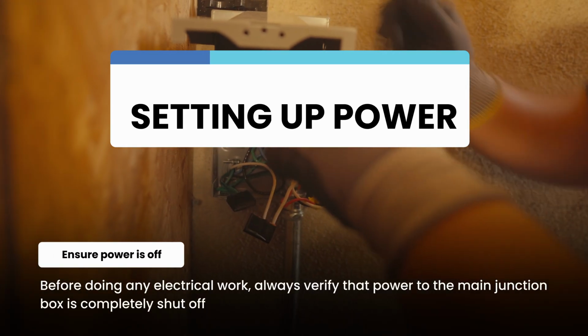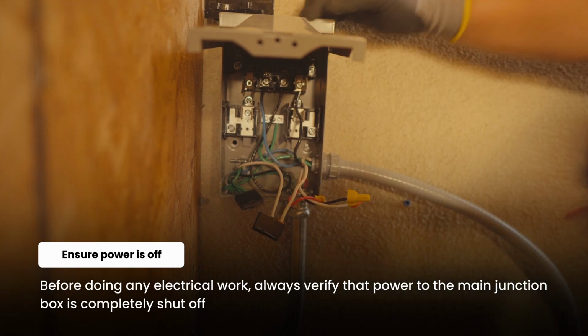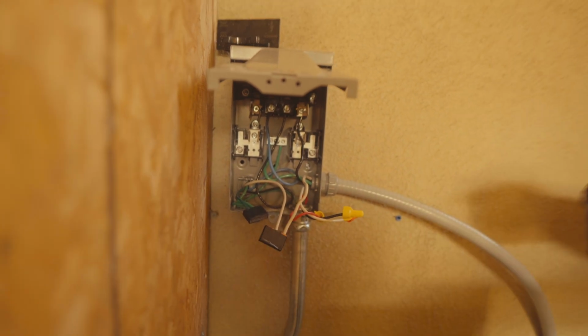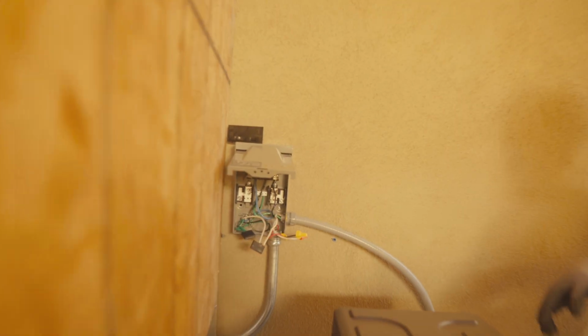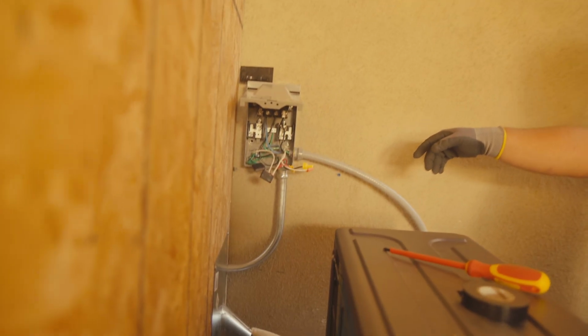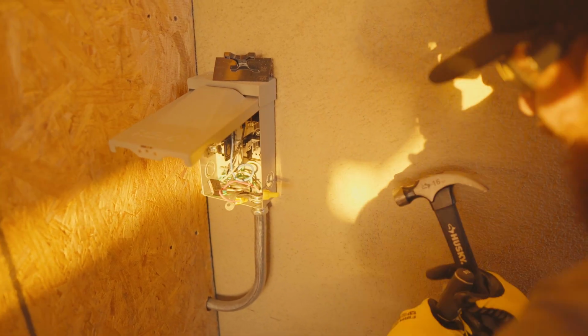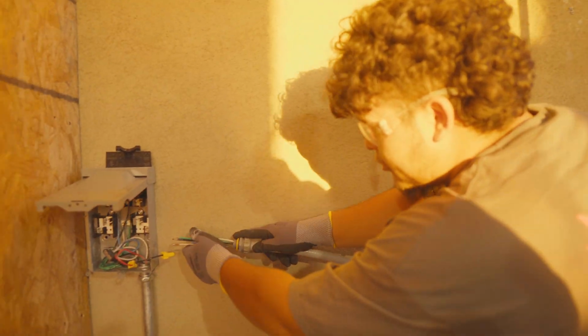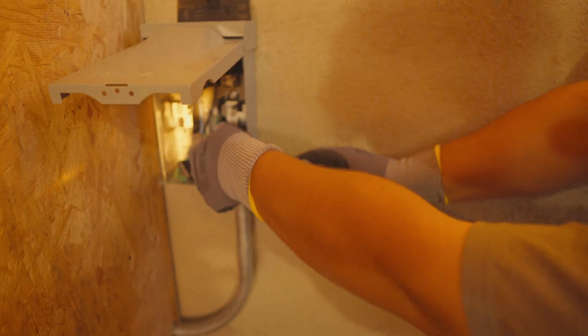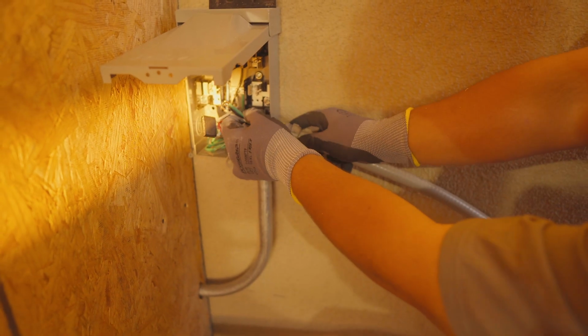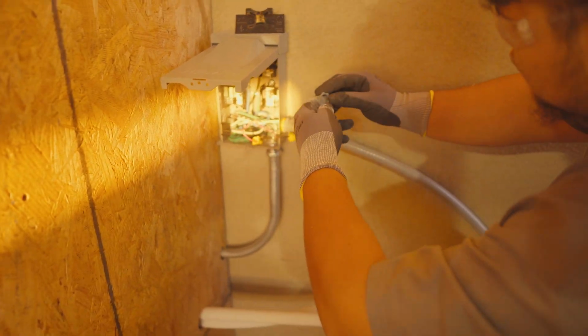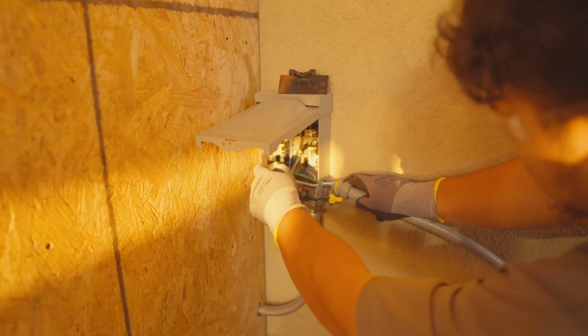Now it's time to connect power to the system. Before doing any electrical work, always verify that power to the main junction box is completely shut off. This is essential for preventing electrical shock or equipment damage. Next, remove the appropriate knockouts on the outdoor heat pump unit and attach the electrical whip. The correct knockout ensures a secure, protected entry point for the wiring and helps prevent strain or moisture intrusion.